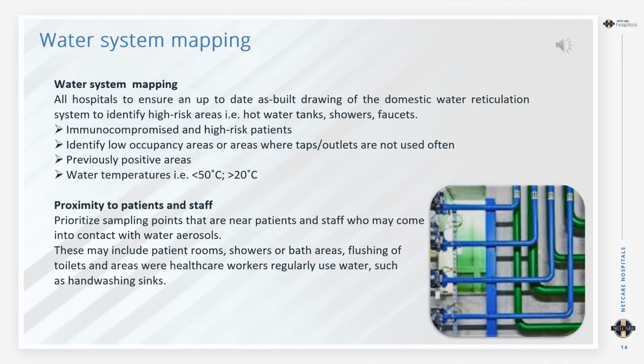The water management committees were established. Water system mapping needed to be done. So that is an up-to-date drawing of the domestic water reticulation system. And on this map, we also identified where immunocompromised and high-risk patients are, low occupancy areas, or where taps and outlets are not used often, previously positive areas, as well as where hot water temperatures were below 50 degrees Celsius or cold water was above 20 degrees Celsius.